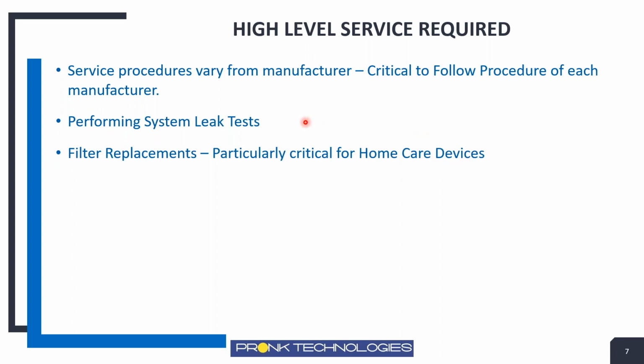In investigating and putting the presentation together and reviewing the FDA incidents, there were a lot of incidents with home care devices, mostly because you can't really have much control of the environment, and a lot of ingress of contamination into the ventilation machine because of bad, dirty filters or lack of replacing of filters.